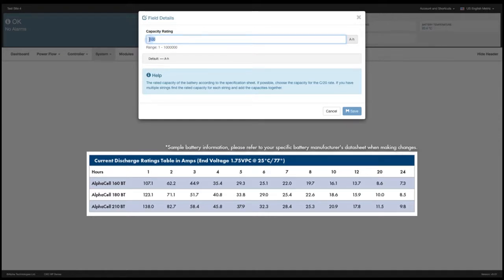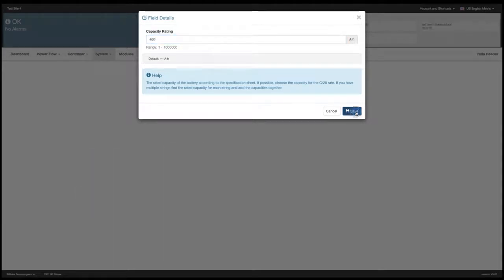I multiply those two values together and I get 230 amp hours. And then I multiply that by 2 for the two strings and I end up with 460. That is the value I enter and hit save.